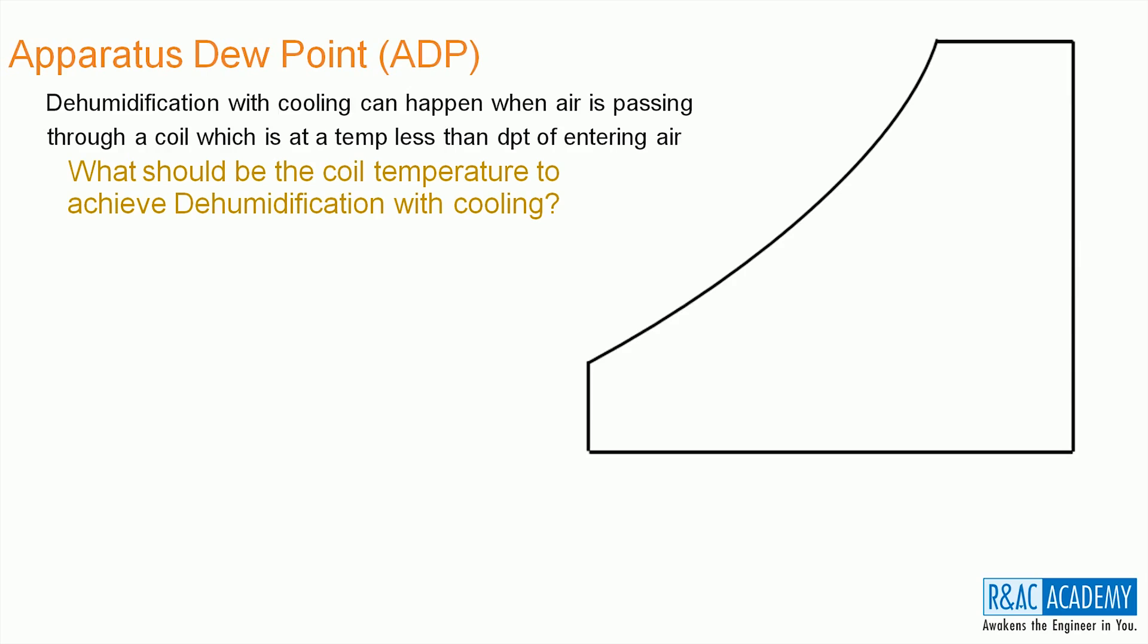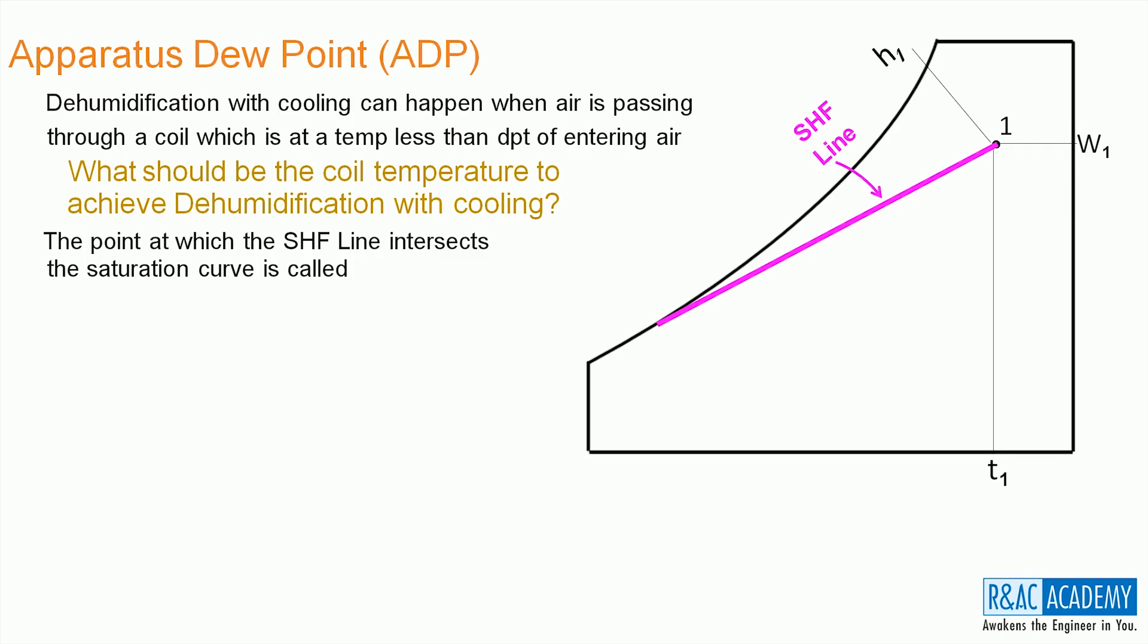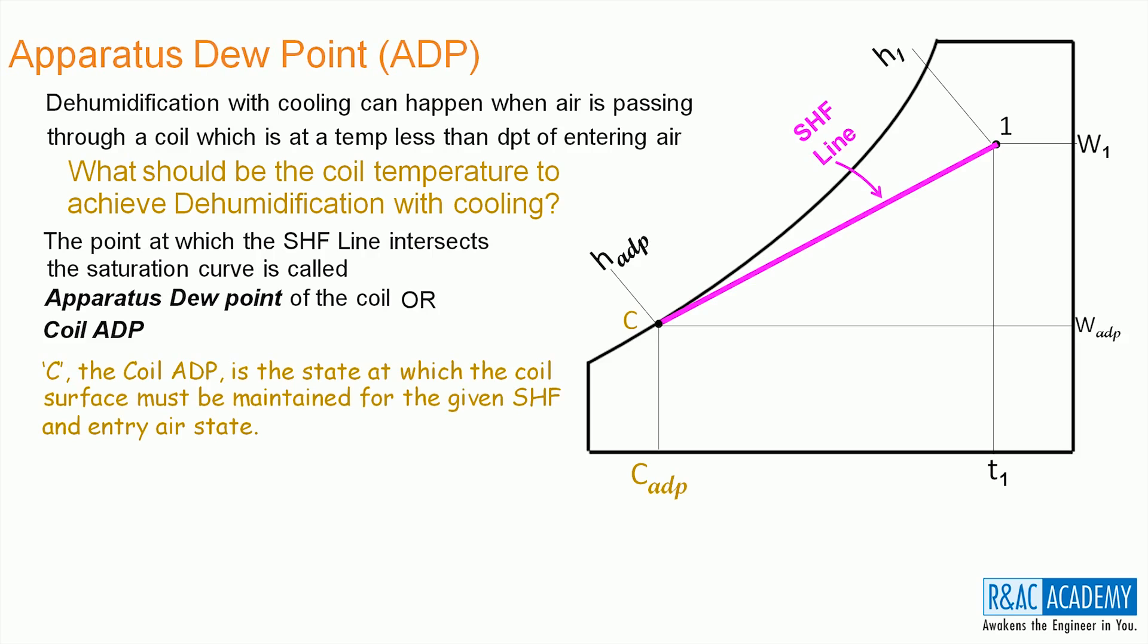Let me explain this process. Let 1 be the state of the air at coil entry and T1, W1 and H1 be the properties corresponding to state point 1. Let us now draw the SHF line starting from 1 until it intersects the saturation curve. The point at which the SHF line intersects the saturation curve is called the apparatus dew point of the coil or simply coil ADP. Therefore, for the given SHF and entry air state, the coil ADP is the state at which the coil surface must be maintained in order to achieve the required dehumidification optimally.